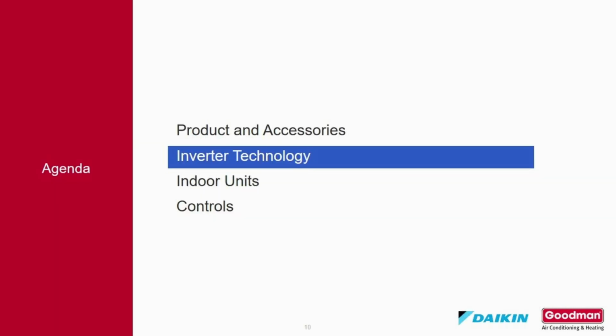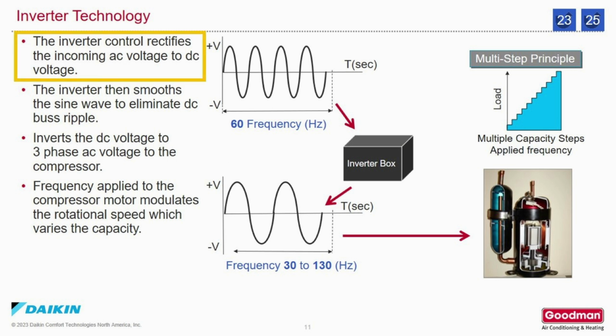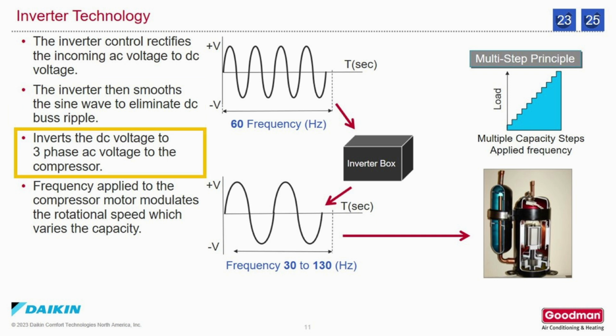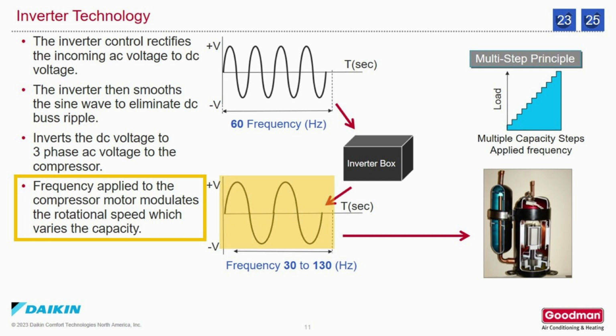Inverter Technology. The inverter control rectifies or changes the incoming AC single-phase voltage to DC. The inverter then smooths the sine wave to eliminate DC bus ripple or pulsation. It inverts the DC voltage into 3-phase AC voltage to run the compressor motor. The frequency applied to the compressor motor modulates the rotational speed, which varies the capacity of the compressor. The frequency is variable from 30 to 130 Hertz.